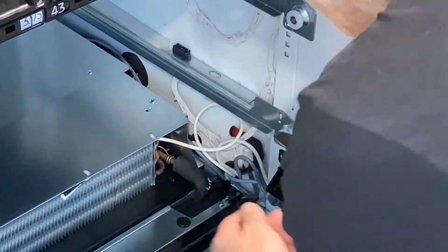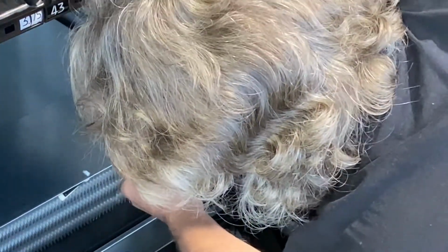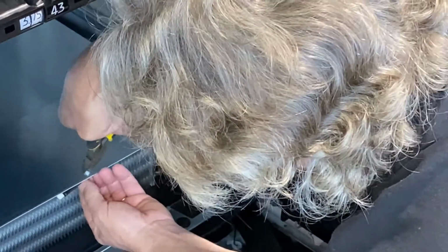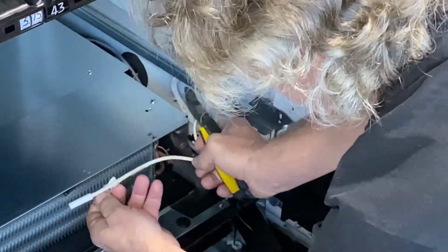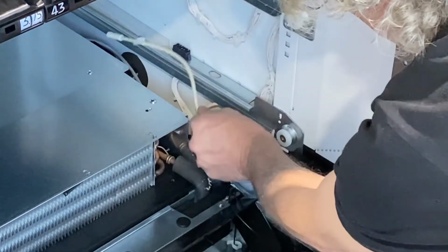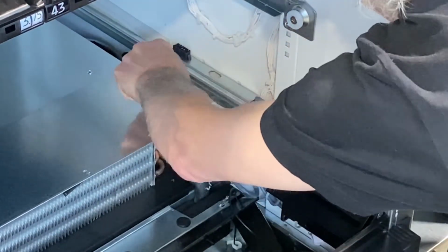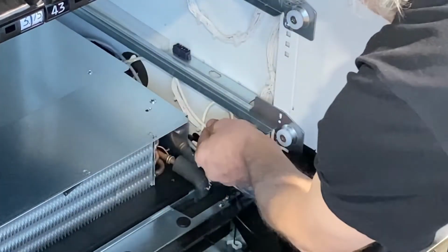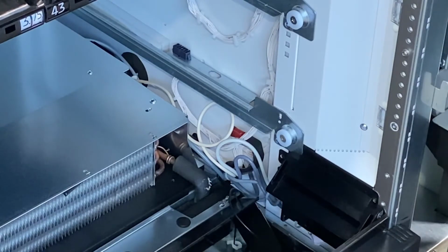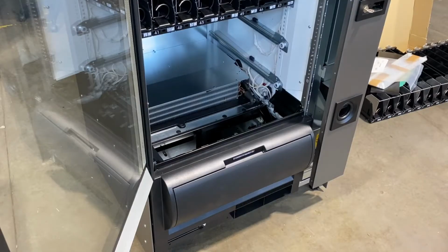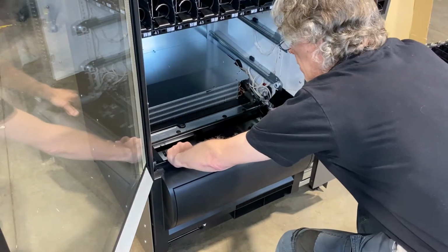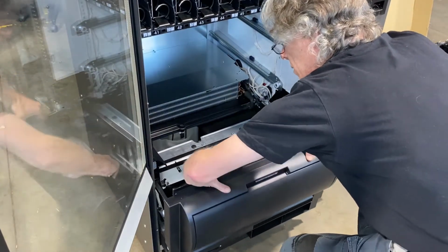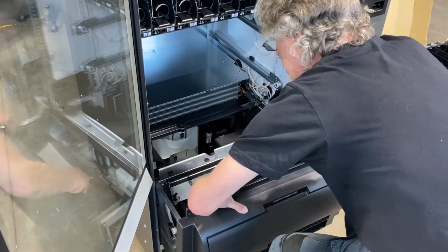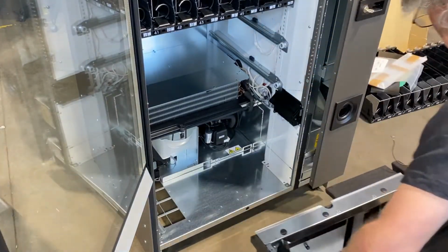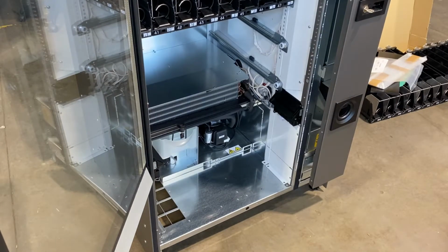We now need to remove the temperature probe, making sure you take note of how it's mounted and where it's mounted, and of course have new cable ties ready with you. Set it aside so it won't interfere with the chiller getting out. Now that's all done, we gently slide the whole delivery bin out evenly, as it's a very tight fit, without damaging any foam components.